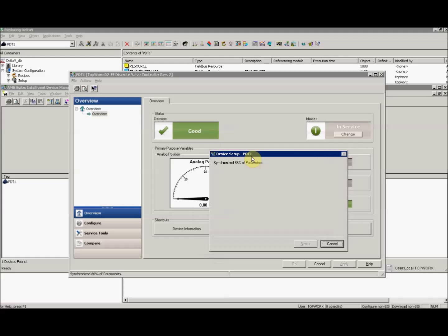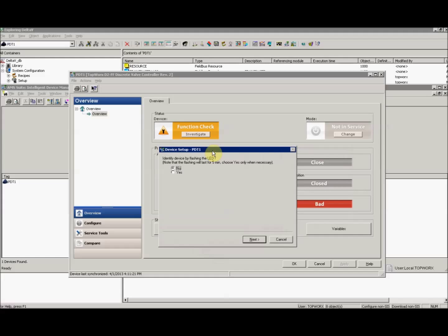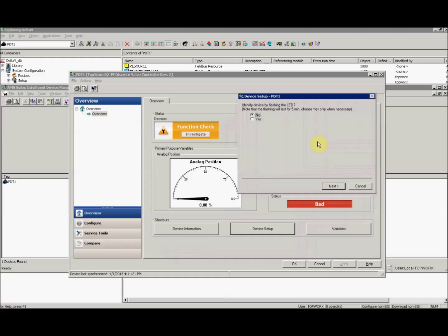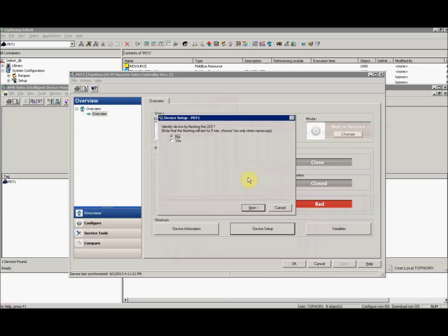The first thing the unit's going to do is place the resource and the transducer block out of service. Click Next to confirm this out of service mode. Next question, it's asking you if you want to flash the LEDs. If you were setting up multiple devices that all look the same, you could flash LEDs to confirm which one you were actually dealing with. In this case, since we're only working on one, we'll select No and click Next. Also, you may notice your status has gone from good to bad, and the device is prompting you for a function check. Both those are functions of being out of service, so don't worry about those right now.